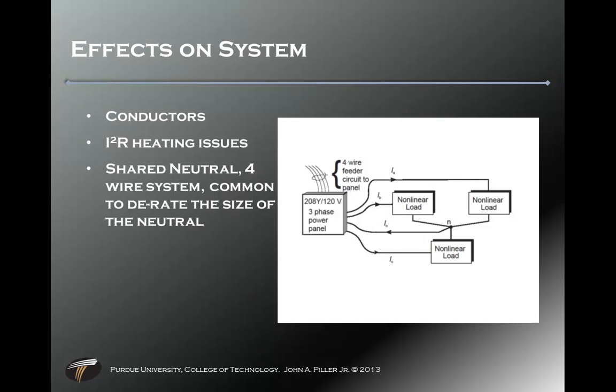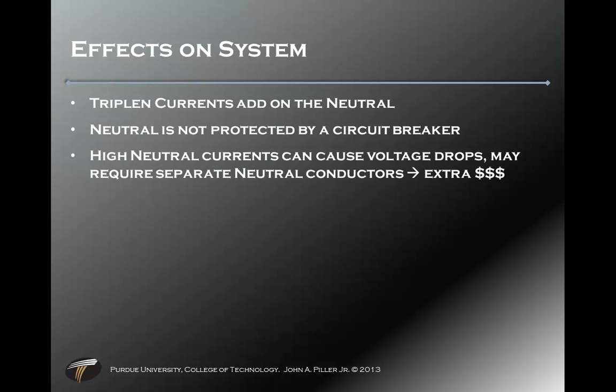Other effects are on conductors — I²R heating issues. In a four-wire system with a shared neutral, the neutral is generally derated because for a truly balanced load there should be no current flow on it. But nonlinear loads cause the potential of burning the neutral line up. Triplen currents add up on the neutral, which isn't even protected by a circuit breaker. Higher neutral currents cause voltage drops and may require separate neutrals for each conductor — and that's just more money.